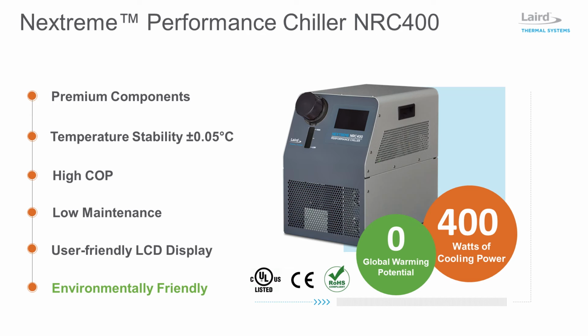Utilizing next-generation thermoelectric coolers and high-performance heat exchanger technology, the unit delivers 400 watts of cooling capacity. Compared to previous versions, the NRC400 offers lower noise operation and a higher coefficient of performance. Solid-state thermoelectric technology provides fewer moving parts, extending the product lifetime and requiring minimal maintenance, reducing the overall operating costs. Users can easily control temperature set points and alarm features via an intuitive LCD touch screen display. The NRC400 is a semi-closed system featuring a larger reservoir tank requiring less refilling during operation and improved temperature stability.